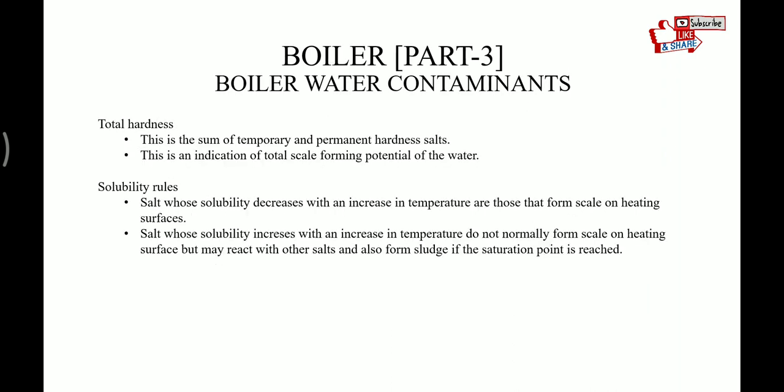Total hardness is the sum of temporary and permanent hardness salts and is an indication of the total scale-forming potential of the water. The solubility rule is very important: salts whose solubility decreases with increase in temperature are those that form scale on heating surfaces. Salts whose solubility increases with increase in temperature do not normally form scale on heating surfaces, but may react with other salts and also form sludge if the saturation point is reached.